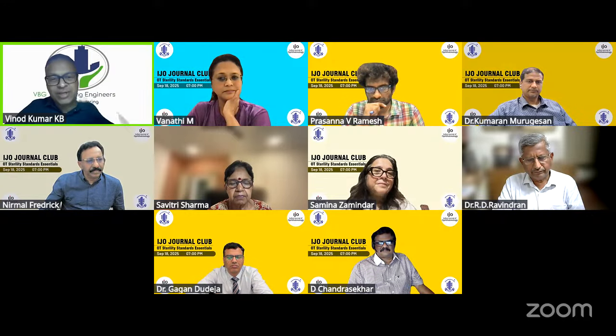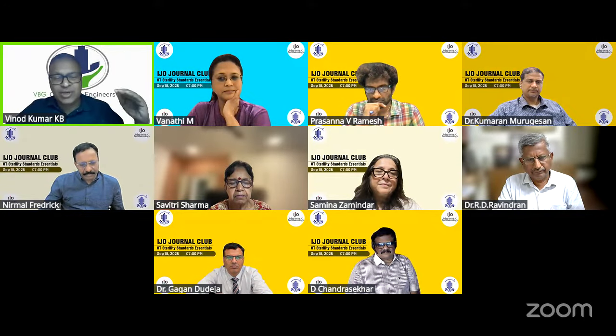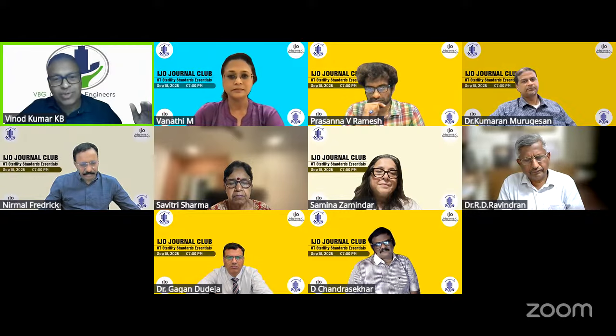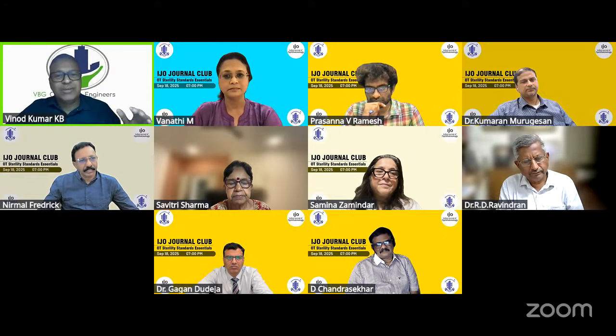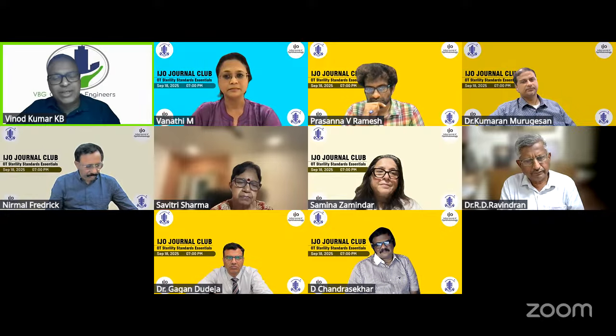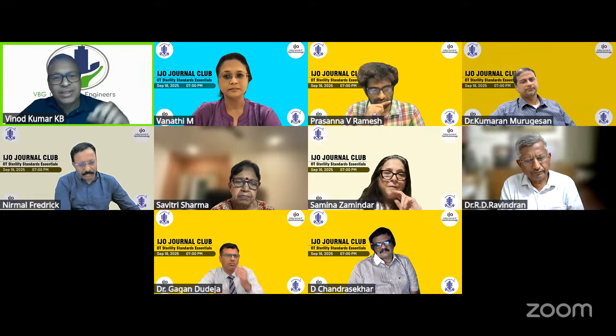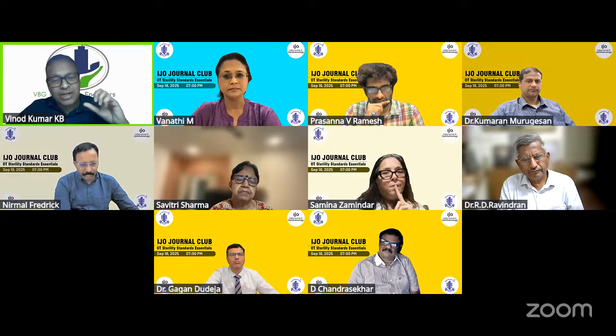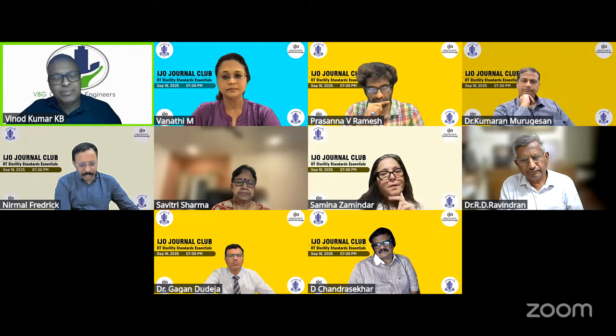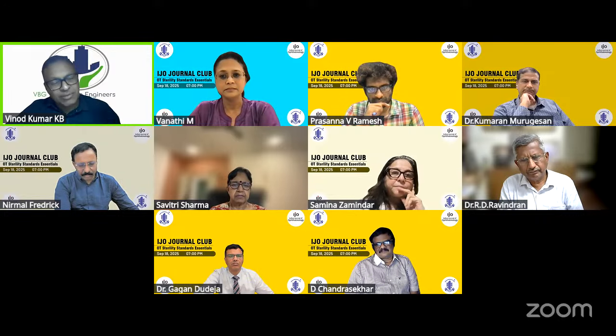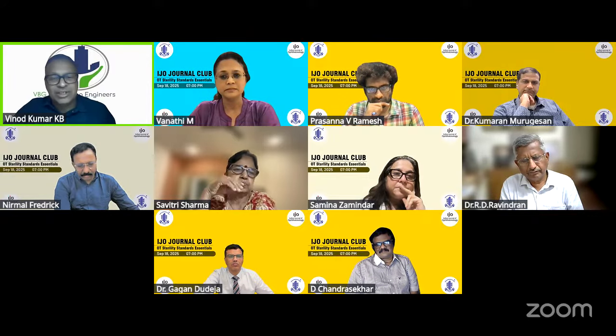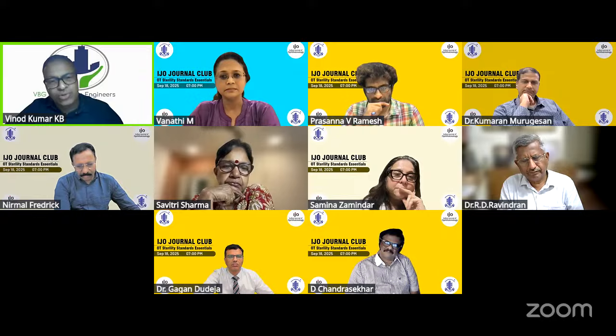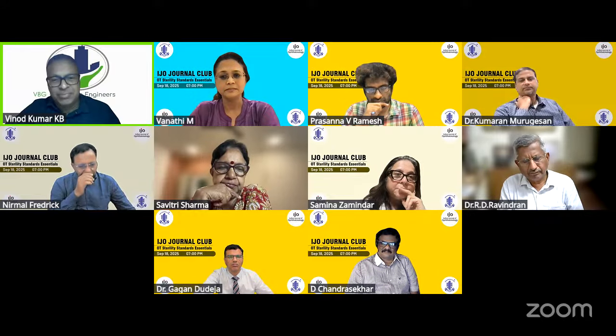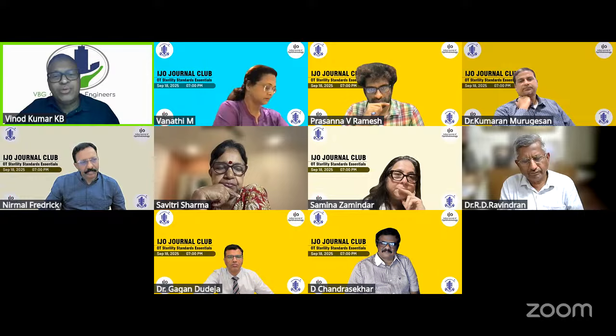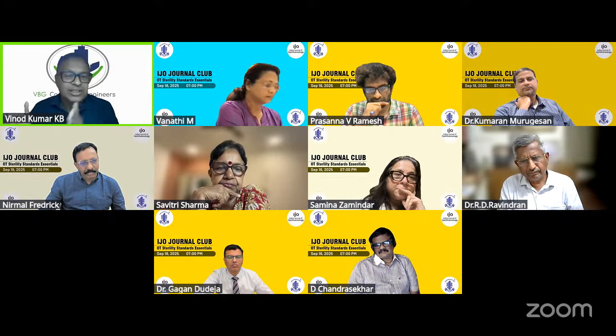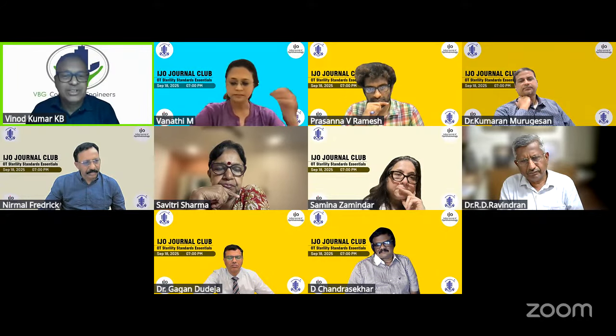When the dry bulb gets lower and lower in an operation theater, the wet bulb also gets lower and starts getting closer to the dry bulb, which is when moisture content starts forming and we reach a dew point temperature. This doesn't happen in an office atmosphere, but unfortunately in theaters where we drop temperatures to 21 and 20, or for super specialty up to 16 and 17, the wet bulb is too low and humidity becomes extremely high. So when you select a healthcare air handling unit, the whole body of the AHU needs to be able to take these low temperatures and high humidities for a longer period of time.